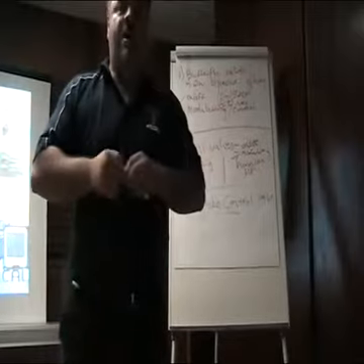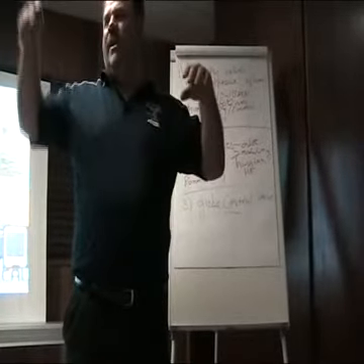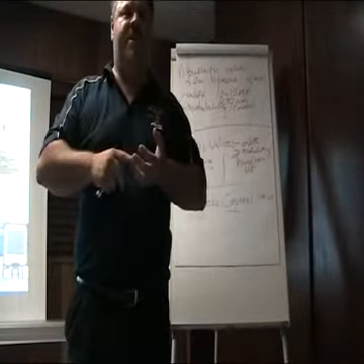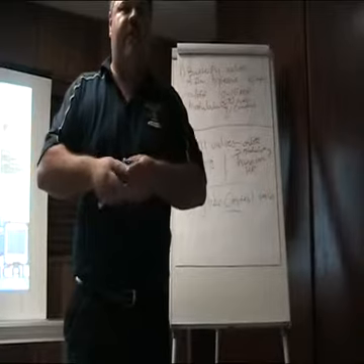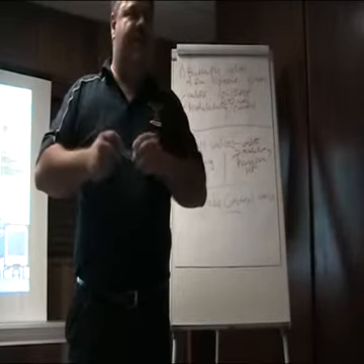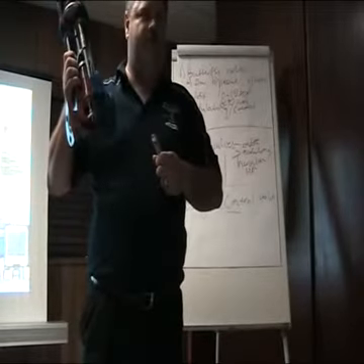Worldwide, guys put fancy things inside this valve to accommodate the following. You will remember this later, whenever Fisher, Dresser, doesn't matter who's going to do the presentation, they will all get to the following stuff. There's cavitation, there's flashing, there's noise control. Sasol's limit is 85 decibel. If you put this valve on a high pressure application and it gives you 101 decibel, you've got a problem. You can't put a standard globe valve in like that.